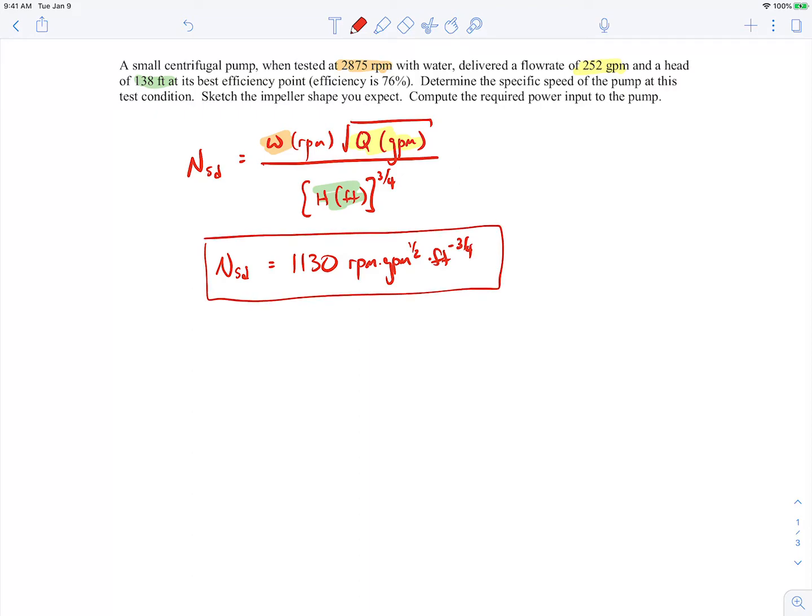You could also do this in the dimensionless form of the specific speed. The conversion between the two looks like this: It's the dimensional specific speed divided by 2,733 RPM gallons per minute to the one-half feet to the minus three-quarters. We could plug this in here and find the dimensionless specific speed as well. And that comes out to be 0.414.